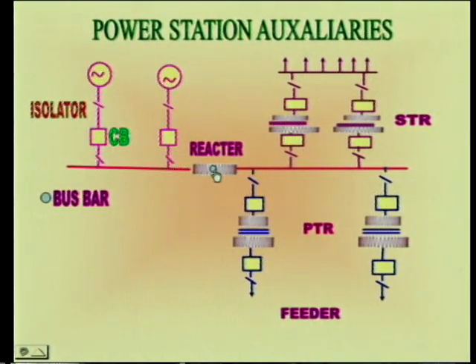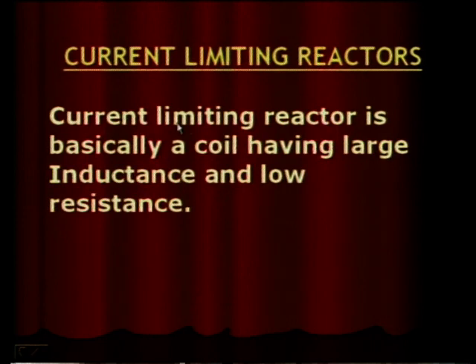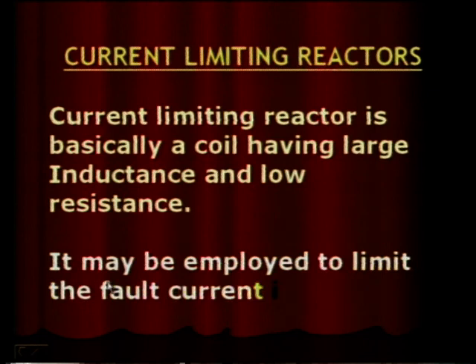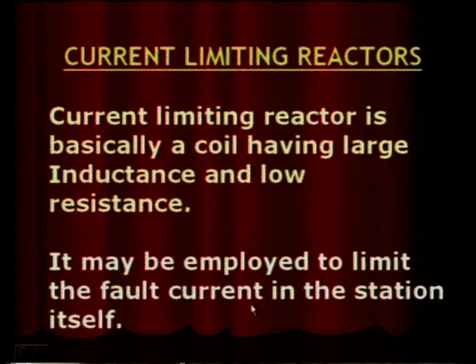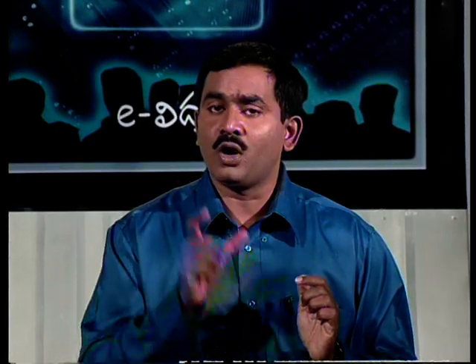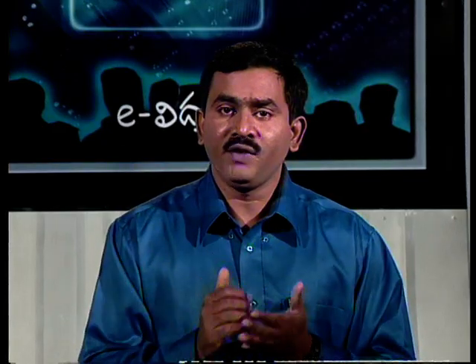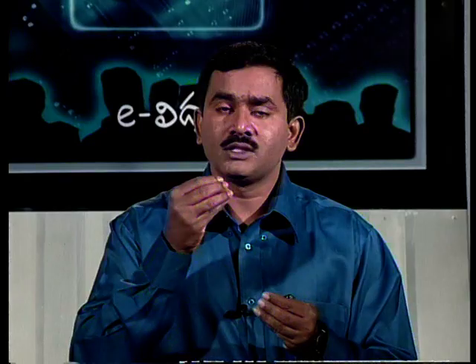Now, another one is the reactor. What is the main function of a reactor? Current limiting reactors. A current limiting reactor is basically a coil having large inductance and low resistance. It may be employed to limit the fault current in the station itself. It is just a current limiting coil. We know that a coil having large inductance and less resistance has a property: a large inductance always opposes an instantaneous change in current. If a fault occurs in the system, it draws many times the load current. Then, due to the presence of this reactor, it opposes the current changing instantaneously from a low value to a high value, hence it limits the short circuit current.